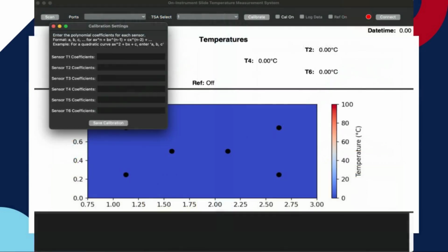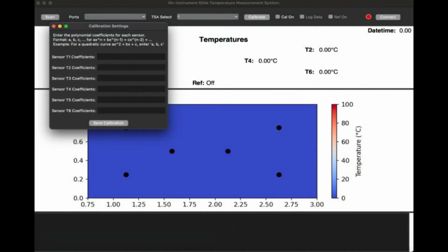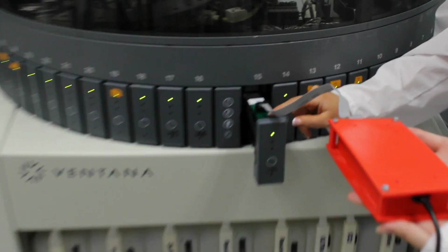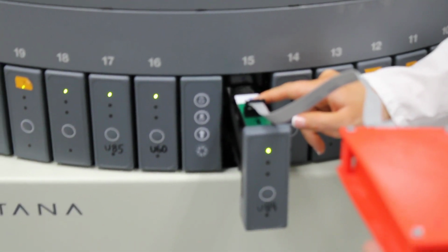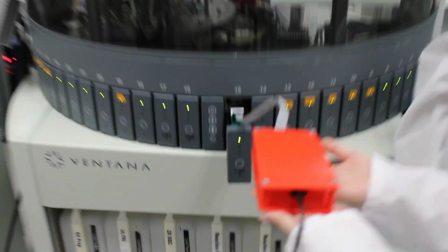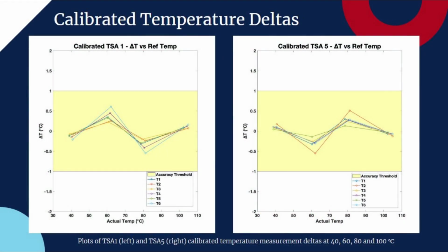desired accuracy. This was accomplished by correlating the raw sensor readings to the reference measurements and generating calibration polynomials for each sensor. A statistical analysis performed on the calibration of each sensor assembly yielded excellent and similar results, further validating the confidence in these calibrations. Calibrating the original raw sensor data with their respective calibration polynomials yielded the results seen here on the screen, where it is evident that each reading falls well within the desired accuracy range, represented here by the yellow shaded region. Further testing, independent of the calibration dataset, has been conducted, and the results continue to support the calibration that has been applied to each assembly.